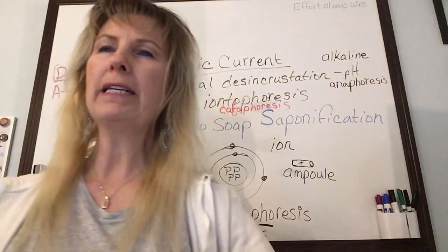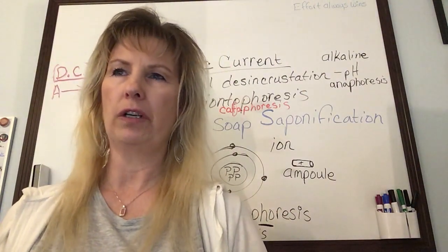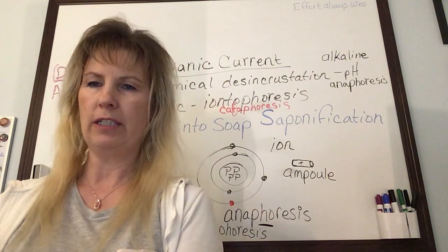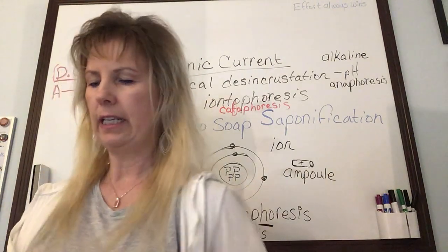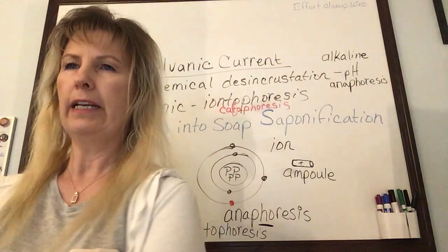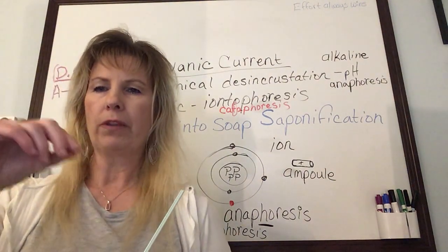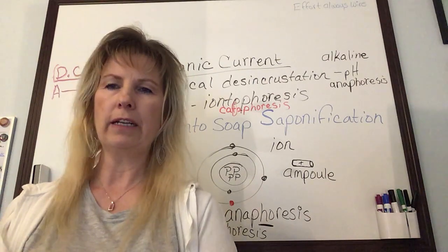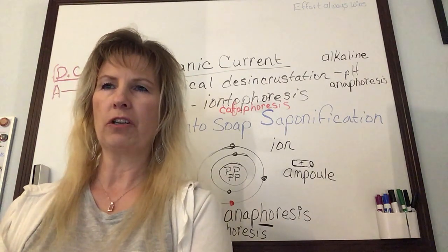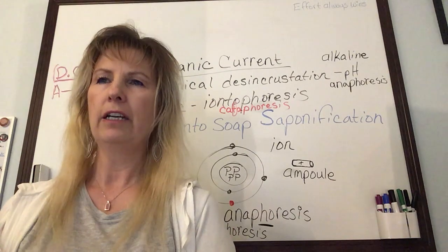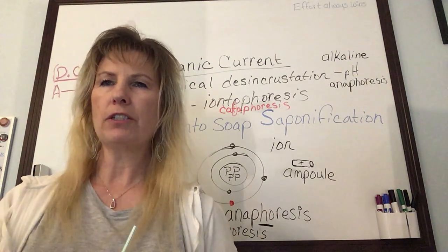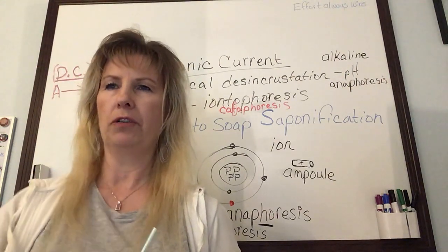Best practices for iontophoresis: keep contact with the skin once the machine is on, because electricity is flowing through the electrodes. Even the slightest removal of the electrode from the skin will cause a tingling or shock sensation. To avoid this, turn off the machine first, then remove the electrode from the skin.